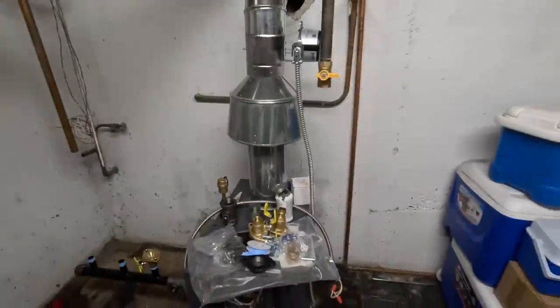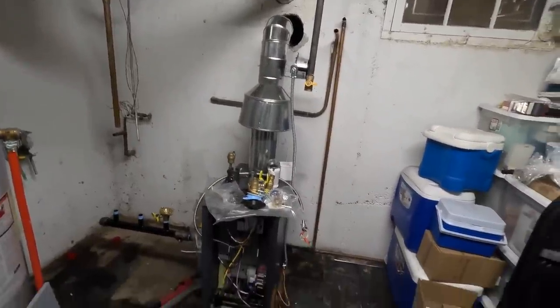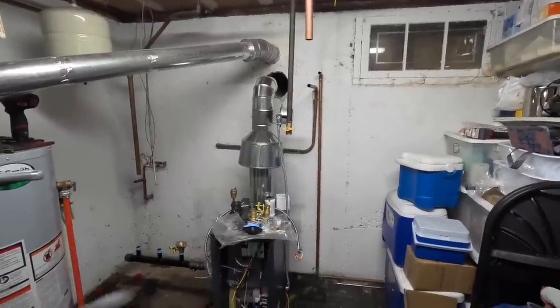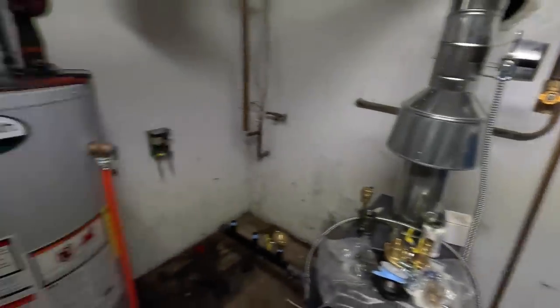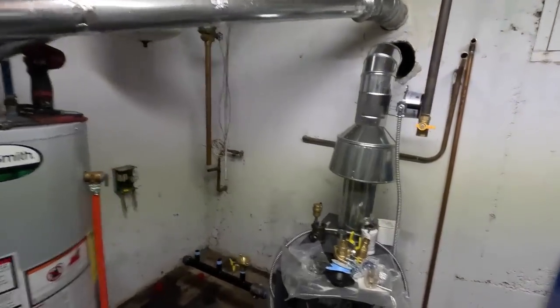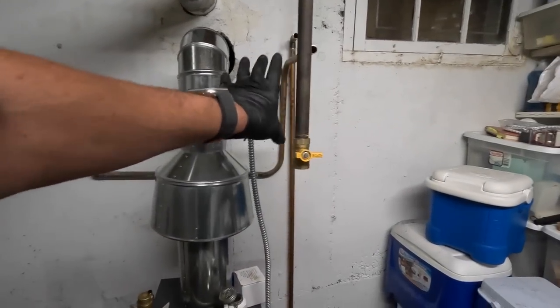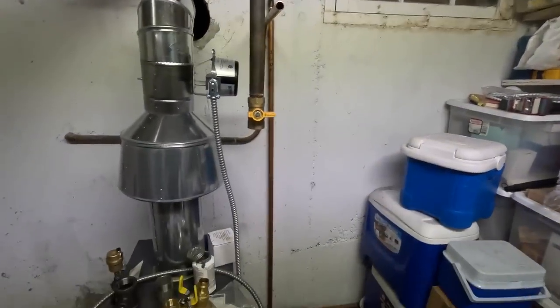Sorry I haven't recorded in a little bit — let me show you what we've got done so far. It's Friday, and of course the reason I don't do boilers on Friday — not only because the Sabbath is the next day and I like to be home early, and something could go wrong especially in the winter when the sun goes down early — but also my mind is already on weekend mode. I didn't think about having inch-and-a-quarter black pipe, and we need inch-and-a-quarter black pipe to come up from the top of this tee about 22 inches to come across and accommodate my air scoop, air separator, tee for the expansion tank, and the boiler feed valve.